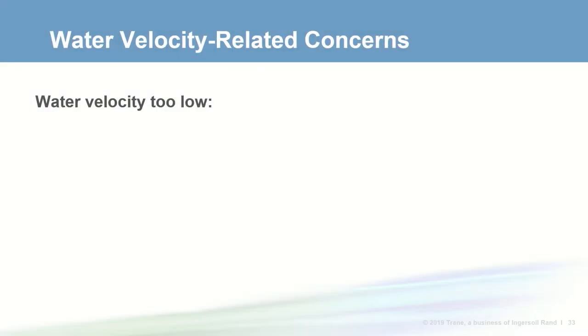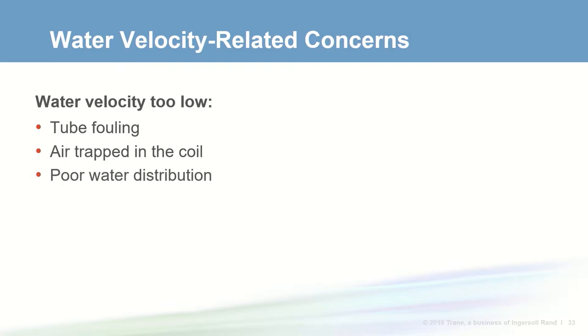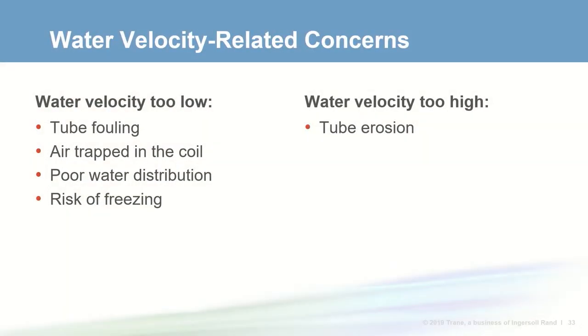The water velocity through coil tubes is determined by the geometry of the coil, including tube diameter and circuiting. Consequences of too low water velocity include tube fouling from sediment or scaling, air trapped inside tubes causing loss of capacity, noise or vibration, poor distribution of water in the coil resulting in non-uniform leaving air temperatures, and a higher risk of water freezing inside the tubes. On the other hand, too high water velocity can cause erosion of inside tube surfaces especially at U-bends, excessive water pressure drop, and noise.